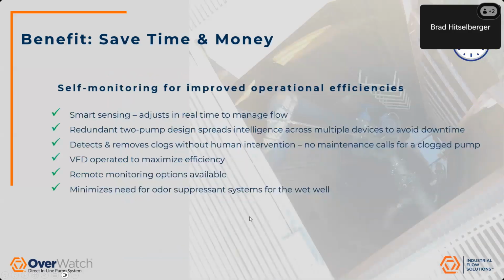So saving time and money, time always equates to money. This is meant so you don't have to do a lot of reactive or proactive maintenance. In our IO&M, we have certain proactive maintenance you should do with this, but we've seen that it is very far less than what you have to do with a traditional wet well. You don't have to deal with cleaning out a wet well, breaking up that concrete layer, having to do any of that you typically have to do.